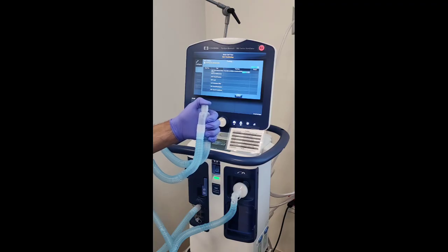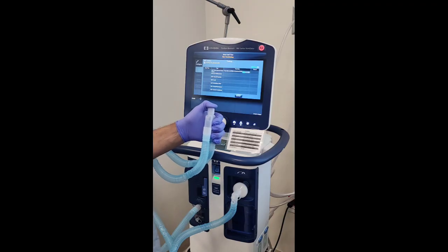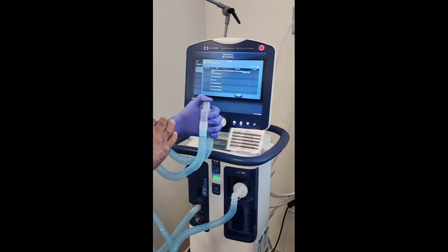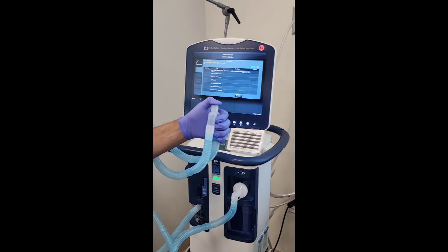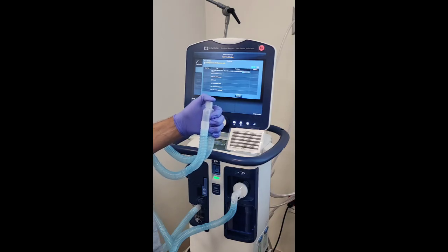So basically it's sending a flow through the circuit, checking to make sure that the flow sensor is working properly. And it must be working. I can feel that it's actually sending a high flow, and then it starts backing off, and you can even hear that it's sending a lower flow through there. Okay, that passed. So now it's going through the EV performance.